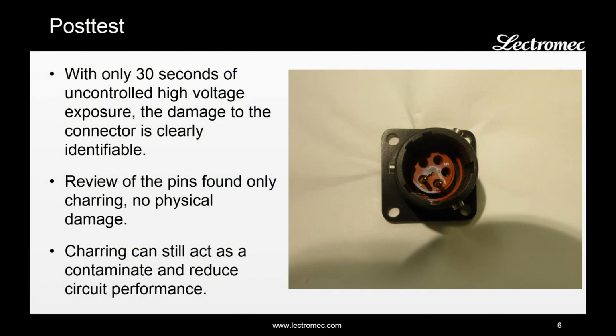With only 30 seconds of uncontrolled high voltage exposure, the damage to the connector is clearly identifiable, particularly the insert. When we pulled out the pins, there was no physical damage to the pins, but there was charring of the pins. This charring can still act as a contaminant and reduce circuit performance.